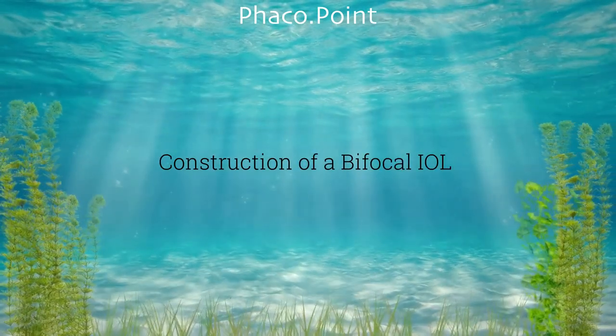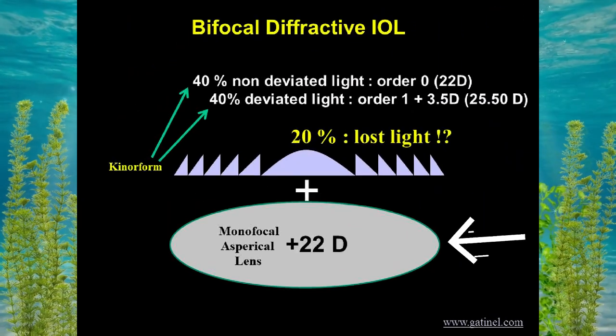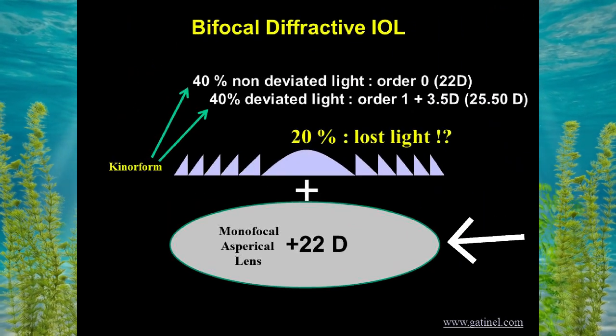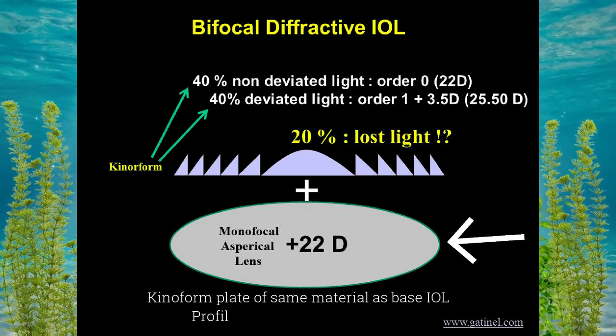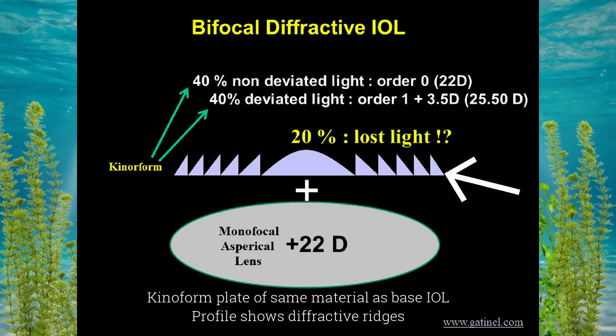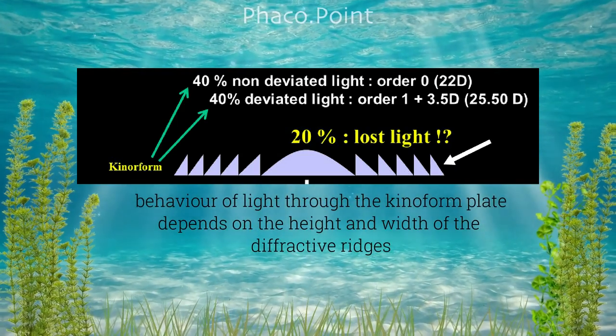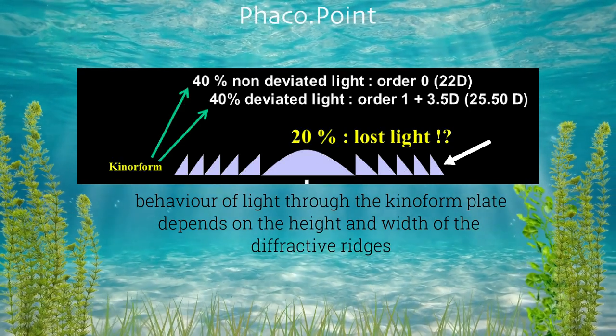The construction of a bifocal consists of a monofocal IOL, whether it's a hydrophilic or hydrophobic acrylic lens, on which a diffractive kinoform plate is added. The monofocal lens will focus the light on the retina.